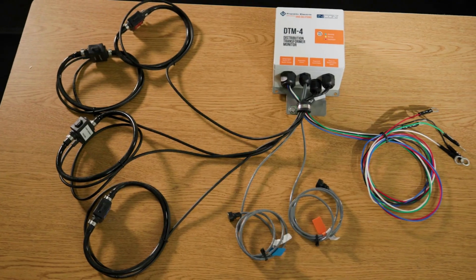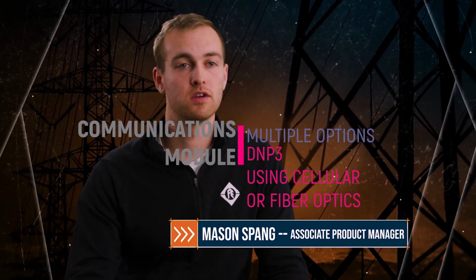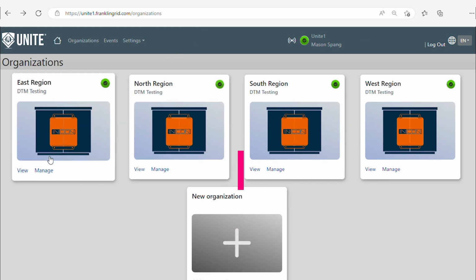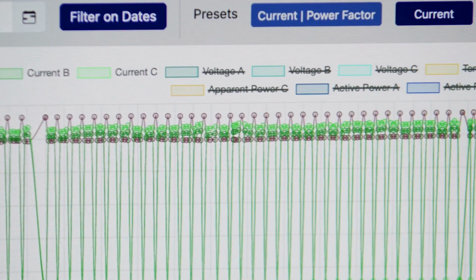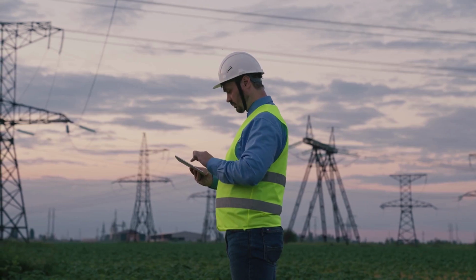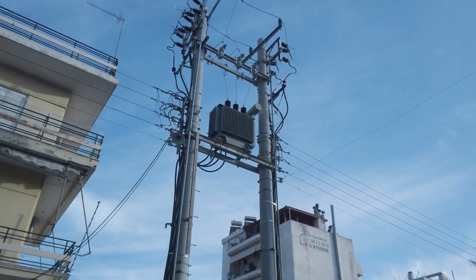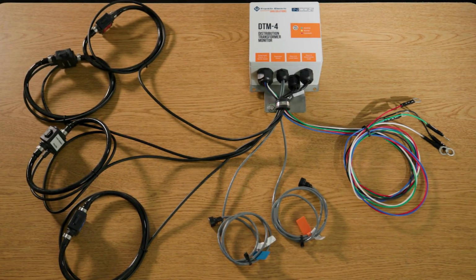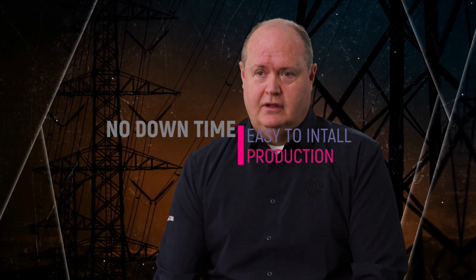The DTM uses DNP3 as well as a Cat M1 and NB2 cellular modem to communicate via cellular network. So you can either use our platform Unite or use your management software system. The distribution transformer monitor includes a cellular communication module that helps utilities deploy at scale.